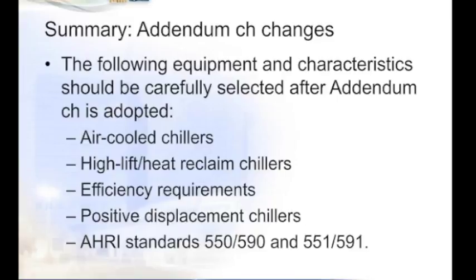And ASHRAE 90.1 will now reference updated AHRI standards, 550/590 and also 551/591. These revisions will help clarify the use of testing standards, and 551/591 provides a metric rating standard with slightly different conditions than those using inch-pound units.